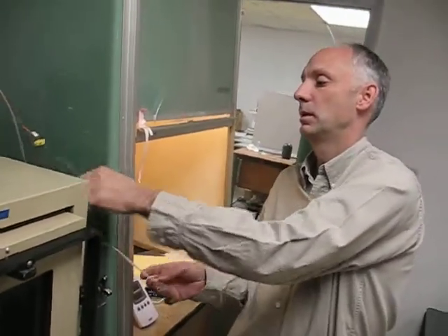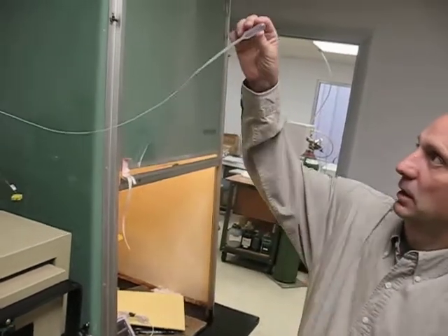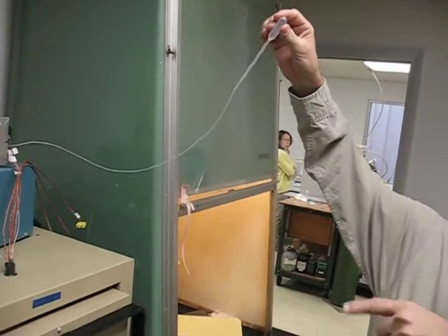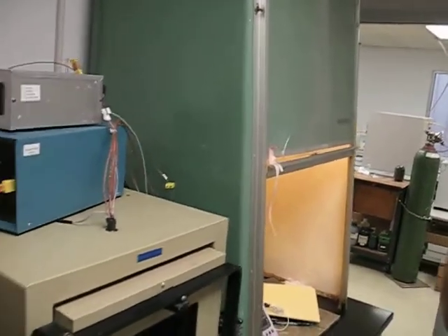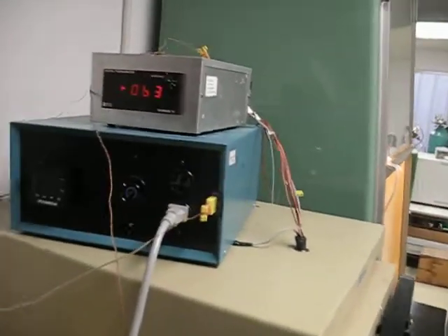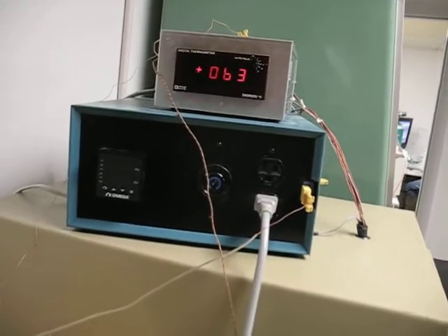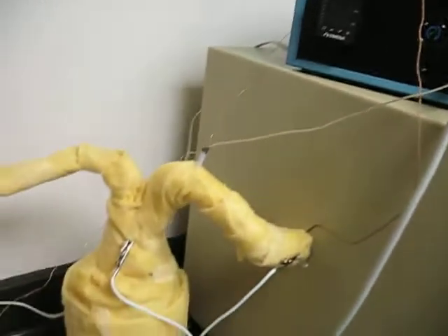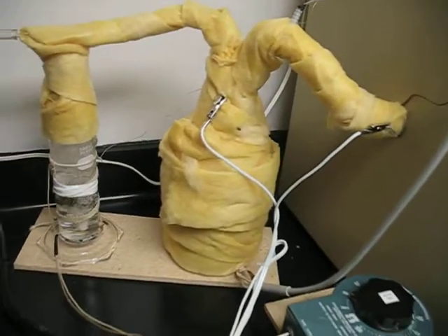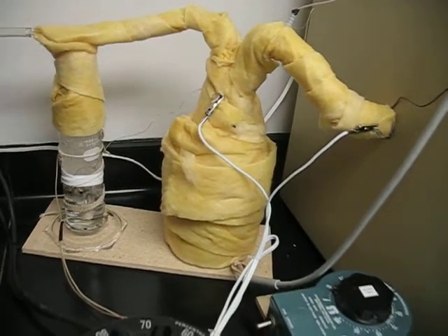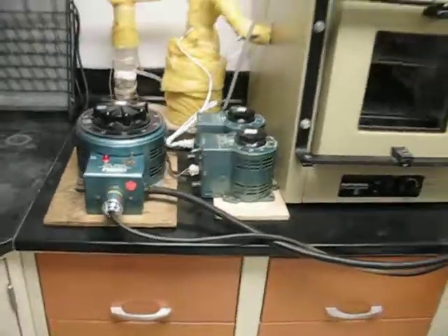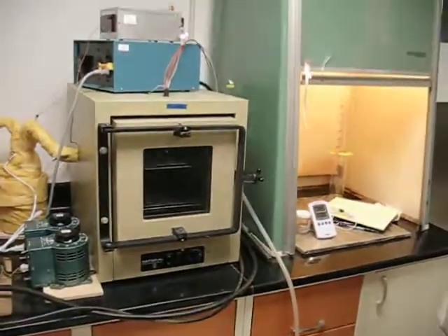The wet bulb, we have the ability to add water, and we can see the bulb and when it is wet, and take a wet bulb and dry bulb measurement and calculate the dew point from that, and see that we're getting reasonable agreement with the desired dew point and our other measurement of relative humidity.